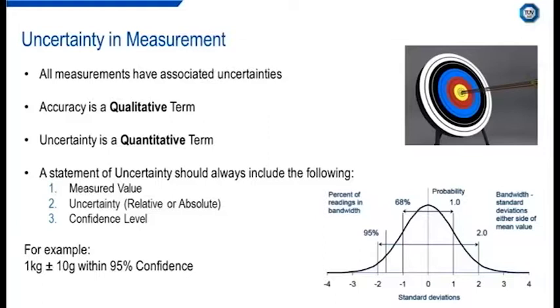The measurement uncertainty can be expressed on a relative or absolute basis. And thirdly, the level of confidence attached to the uncertainty. In industry, the confidence level is usually set at 95%.